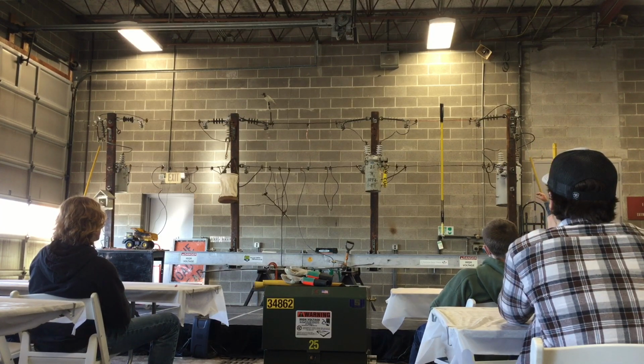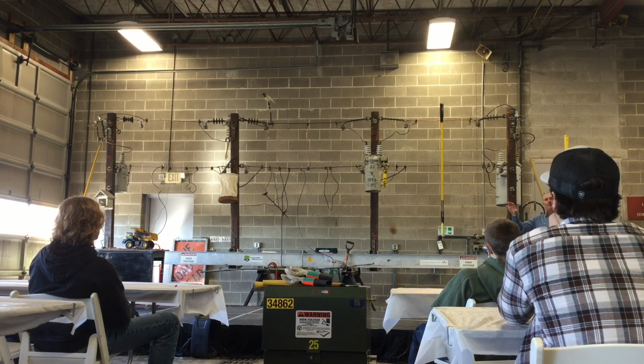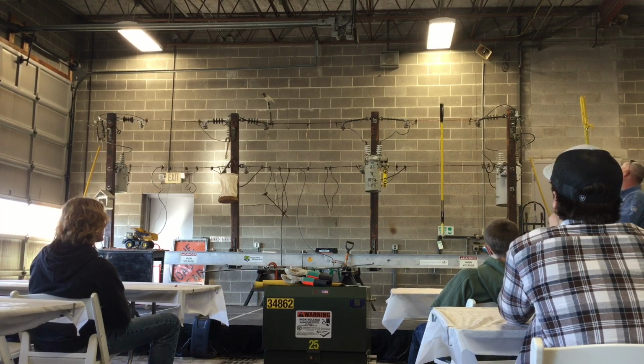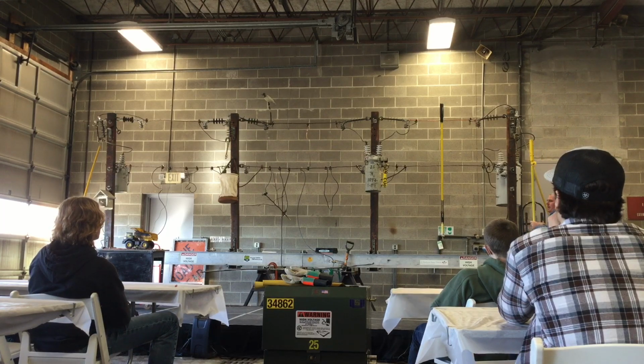Transformers are rated at a voltage, okay? So if this transformer was hanging out in front of your house, feeding your house, we've got 7,200 volts on the line going into the top side, and the transformer is rated at 7,200 primary and 120 volts on the secondary. So the transformer is going to transform the voltage, it's going to step it down. Why? Anybody know why we want to do that?